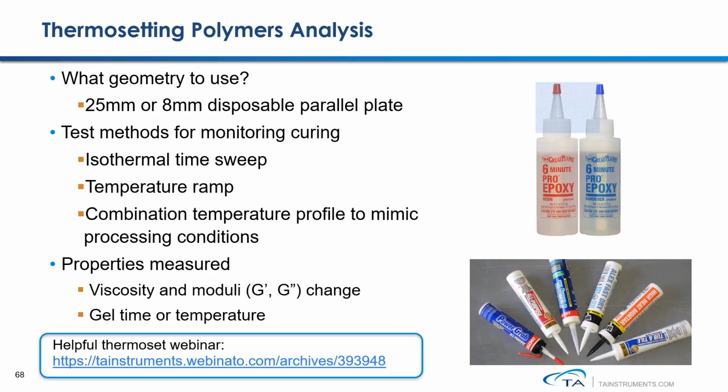Next, let's move on to talk about how we use rheology to study thermosetting curing. First of all, what geometry shall we use? Since this kind of sample is eventually going to cure, you need to consider using a disposable parallel plate. The 25 mm and 8 mm disposable plates are the commonly used geometries for this kind of study.